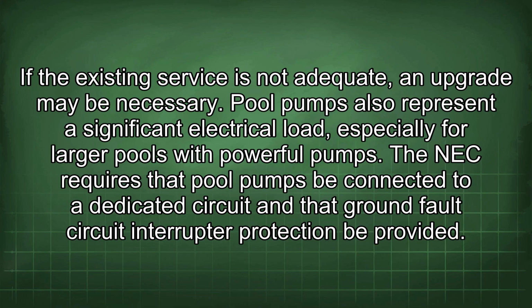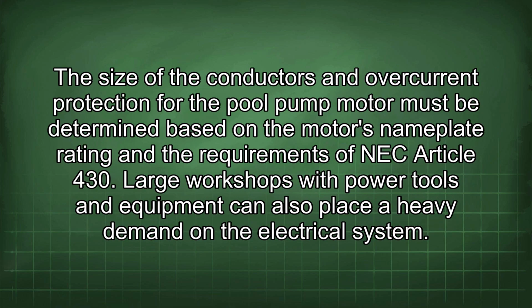Pool pumps also represent a significant electrical load, especially for larger pools with powerful pumps. The NEC requires that pool pumps be connected to a dedicated circuit and that ground fault circuit interrupter protection be provided. The size of the conductors and overcurrent protection for the pool pump motor must be determined based on the motor's nameplate rating and the requirements of NEC Article 430.